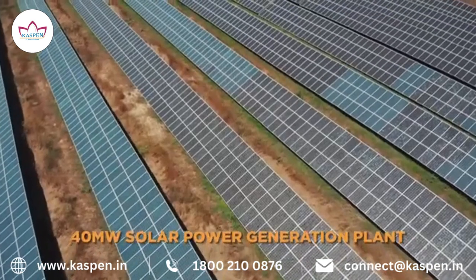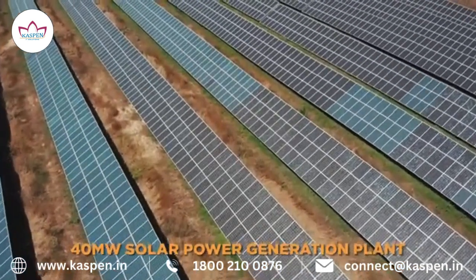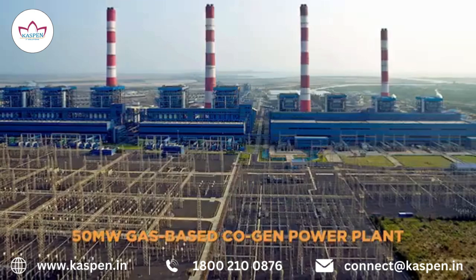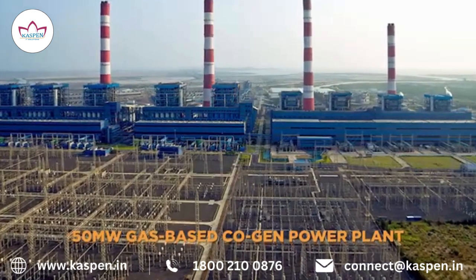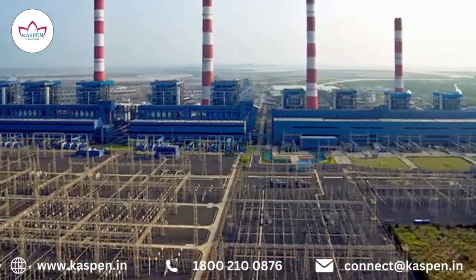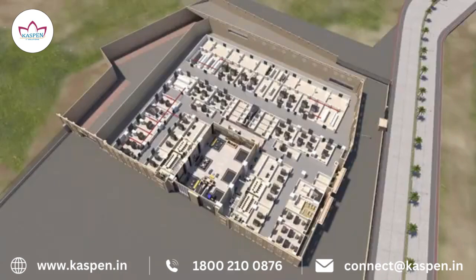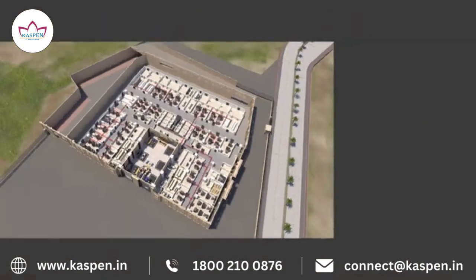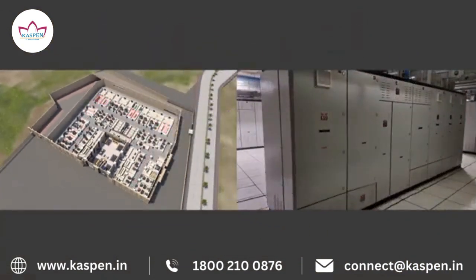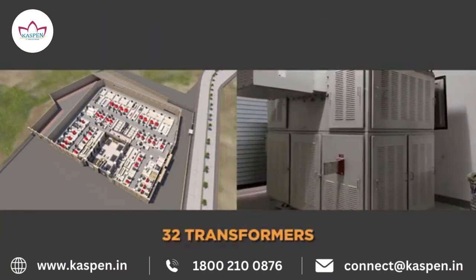Soon, Yotta NM1 will be powered by a captive 40 megawatt solar power plant and a captive 50 megawatt gas-based cogeneration power plant adjacent to our data center park. The 11 kilovolt power terminating at N+N redundant HT panels in the building is stepped down by an array of 32 transformers and through panels and bus ducts.